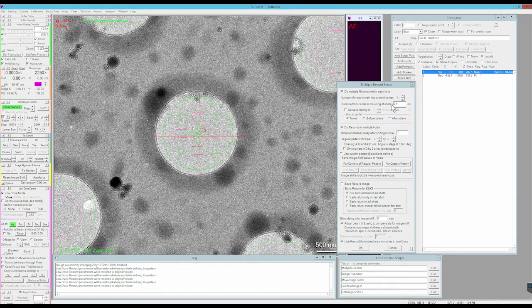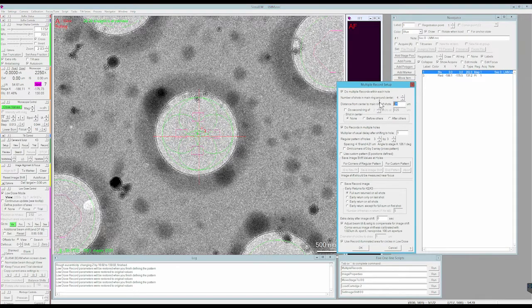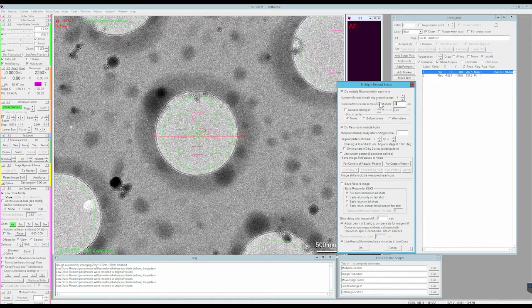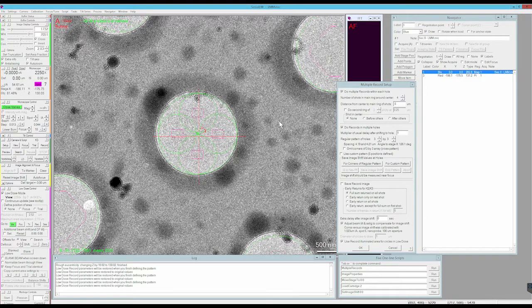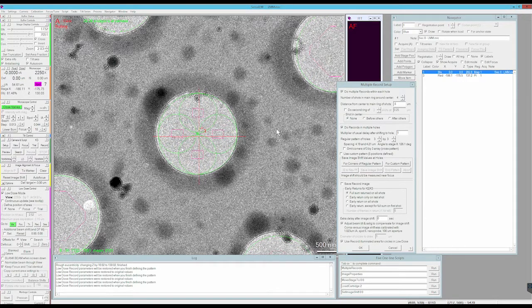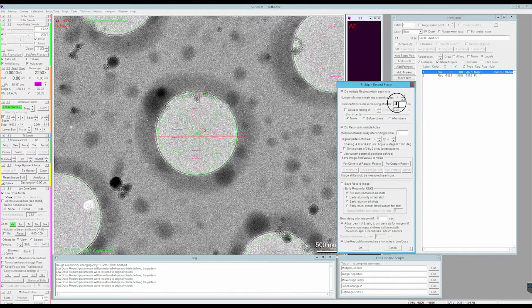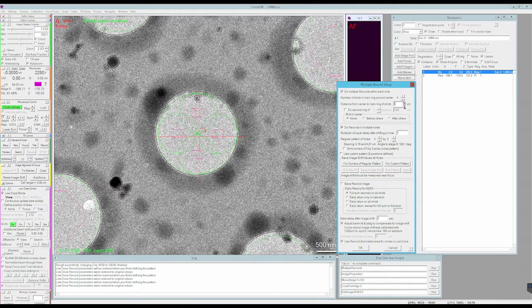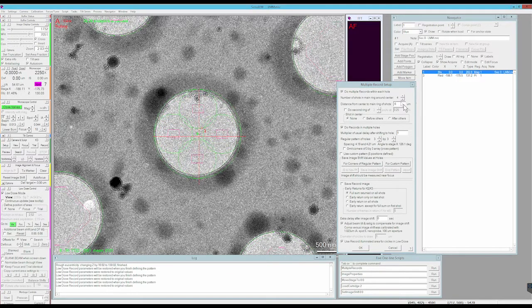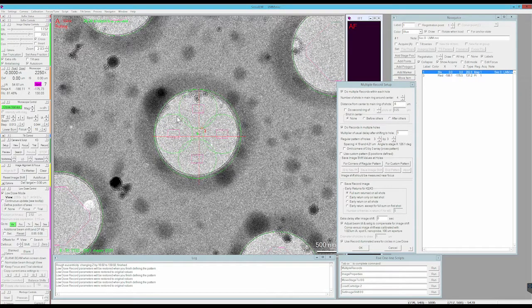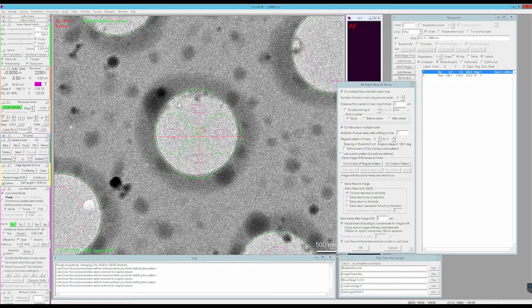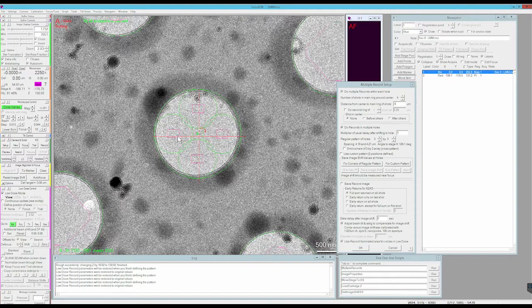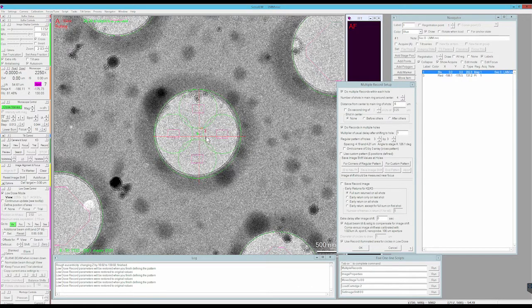There's still a lot of real estate of ice. There's still a lot of ice within the hole that I'm not acquiring at. So let's adjust the distance again to see if we can get rid of this problem. So at 0.5, I'm now doing a bit better. Let's just see what 0.6 does. At 0.6, looking really good.